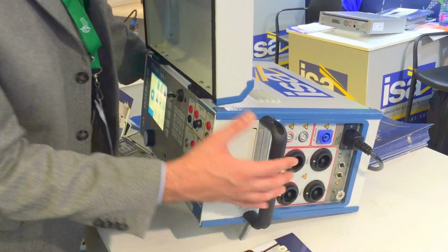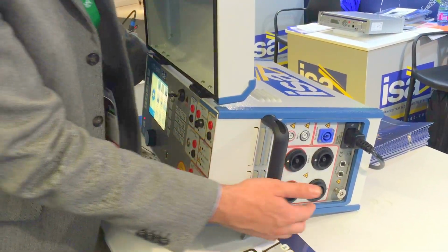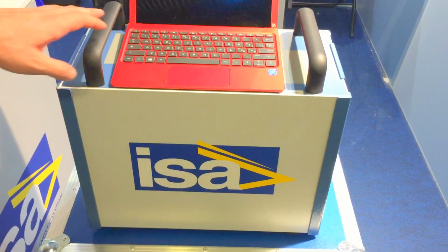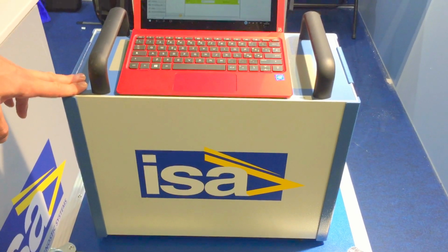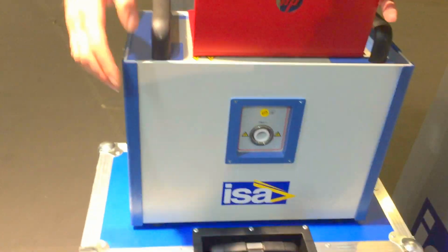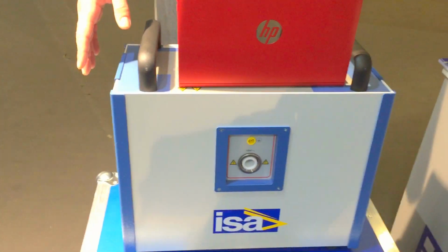In general, 800 amps AC you will probably use while testing a CT, and 400 amps DC you can use while testing resistance of your circuit breaker or a joint on a bus bar. With the addition of TD5000, which is a booster, we generate up to 12 kilovolt, and using that we do a tan delta or dissipation factor or power factor test. So the high voltage output can be seen here, and when we merge these two devices together, they become a very powerful test set which can do all the necessary tests on your power, voltage and current transformer, including circuit breakers and some other substation equipment.